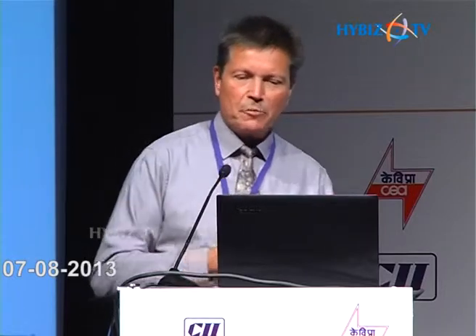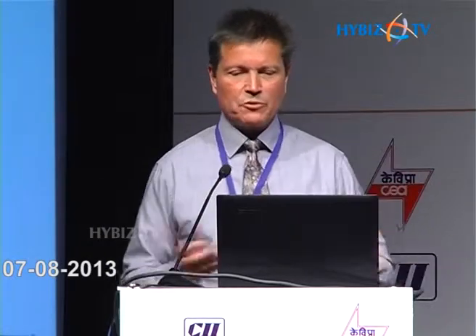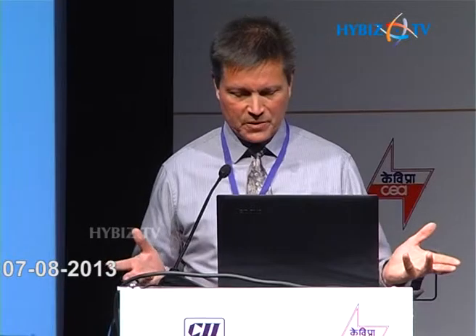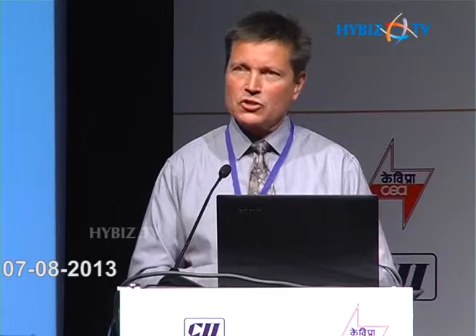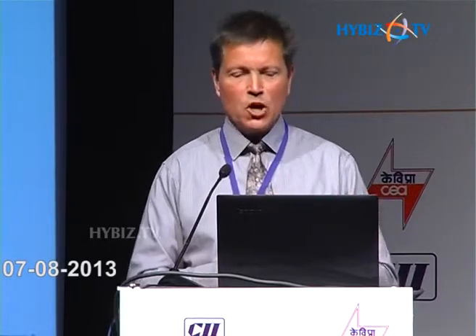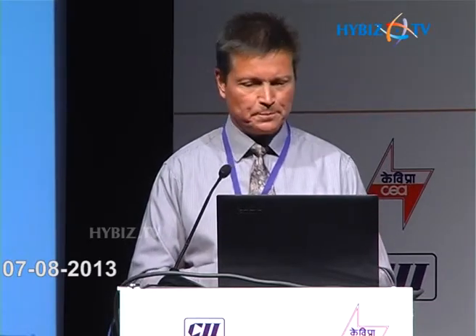So the summary of the benefits of this system that we have today is that it's approved for monitoring total gaseous mercury with a range 0 to 45 micrograms. But it's also approved since a long time ago for other gases like NOx, SO2, CO, water, and other compounds, for instance HF, HCl for waste incineration plants and so on. It is a well-proven analyzer technology. We have been around for almost 25 years.